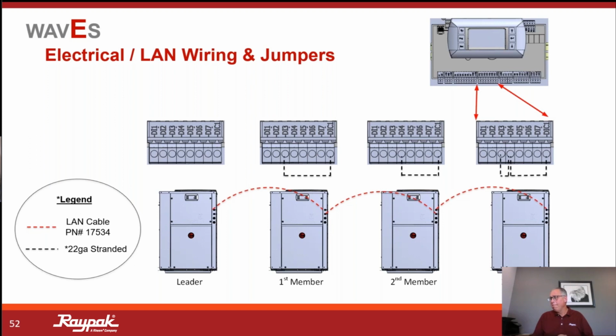What if it loses communication, the cable? How would they react? Good question. The way I'm understanding it is that if we have power to the first unit, but the unit goes offline and still has power, it's still going to function as the leader, and all of these are going to understand that it's still connected, even though this one is not in operation. If we lose power here, then we lose that communication and our units are then offline. We are not then communicating that there is a load or a demand. That's how it was explained to me. All right, got it.